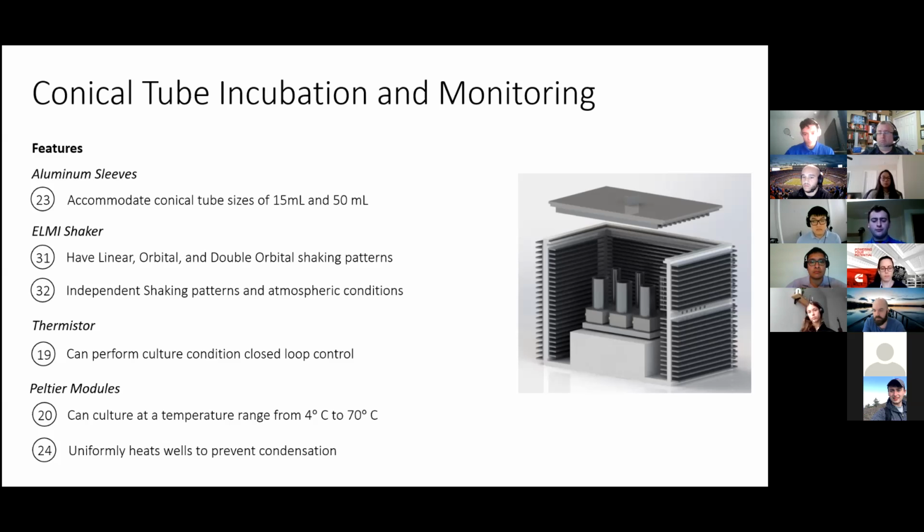So what are these fins doing for you exactly? They allow us to get the heat out, since we have essentially what is a refrigerator in a box, the classic thermodynamics problem. We have heating elements inside of a small space. And so when we start cooling the design, we need to get the heat out. You just told me that was a very inefficient way of doing that. I'm sorry, could you clarify? You just said that you don't get a lot of heat transfer across those fins. No, not for small incubation times. We rely mainly on the conductivity through the base and then out through the outside fins.